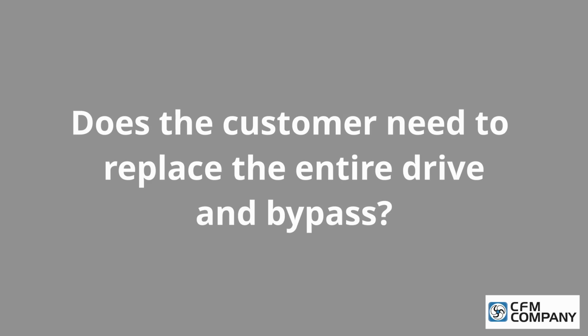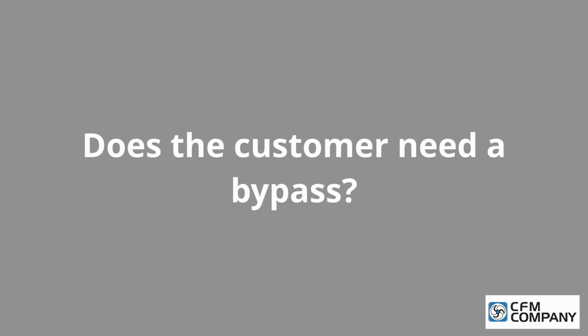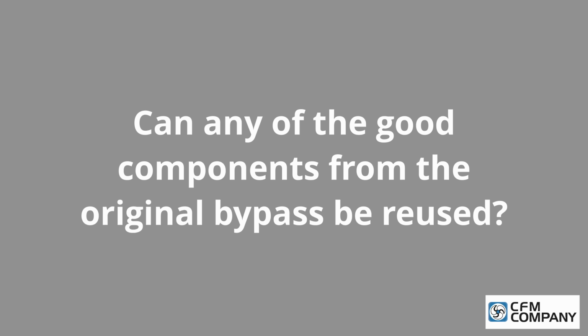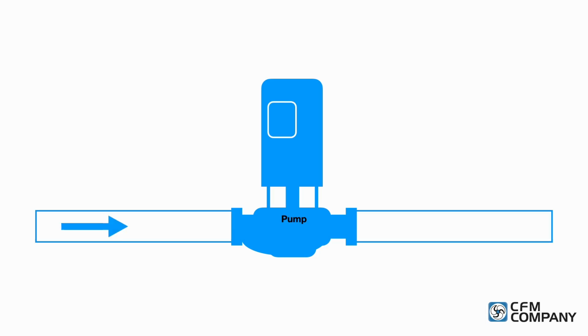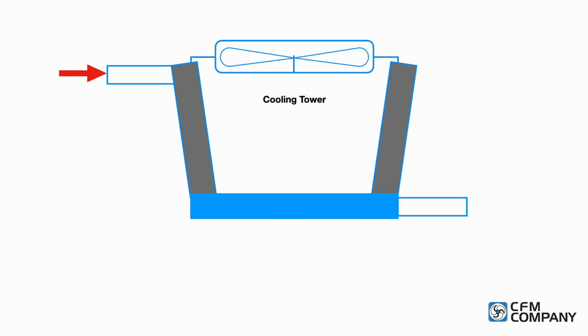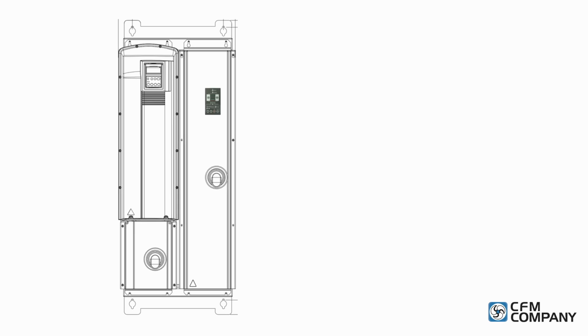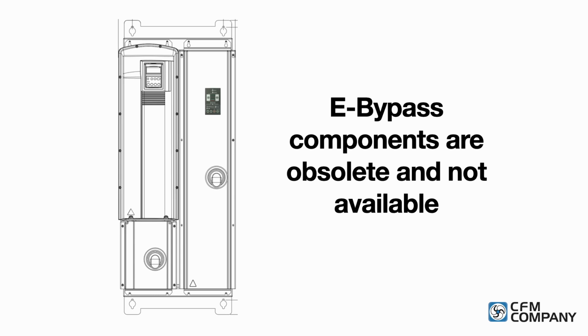Does the customer need to replace the entire drive and bypass? Does the customer need a bypass? Can any of the good components from the original bypass be reused? For customers who require the redundancy of a bypass, applications such as a pump or a cooling tower, the stay-in-place bypass replacement covered in this video will not work. Even though the original electronic bypass may be functional, the internal bypass components are obsolete and not available.